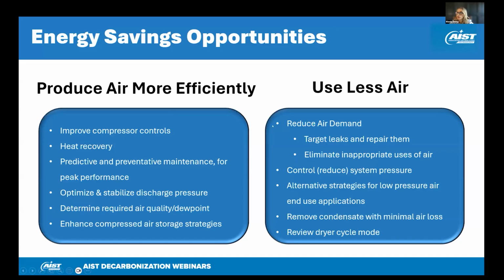As far as using less air, this is reducing the power input for your system to deliver the same amount of flow that's required for your process. So what you can do here is target leaks and repair them, eliminate inappropriate uses of compressed air, look at reducing the system pressure, looking at using low pressure air where high pressure compressed air is used for certain applications that don't need the high pressure air.